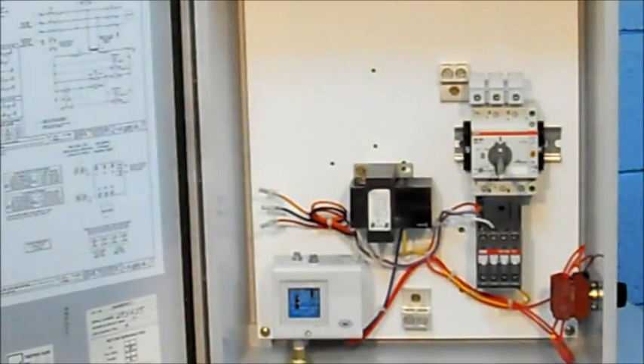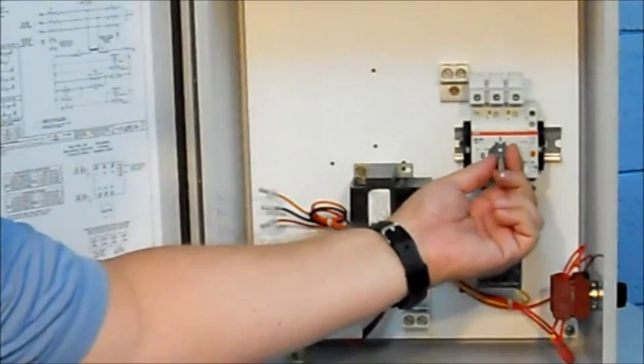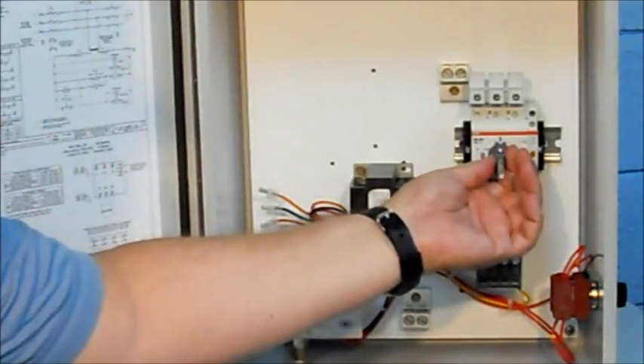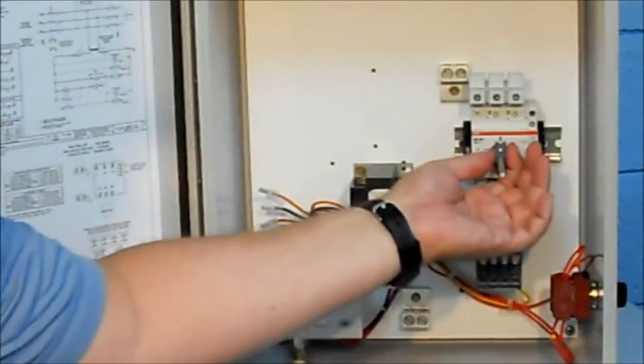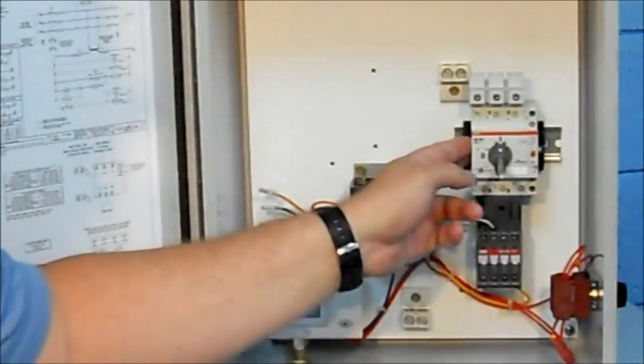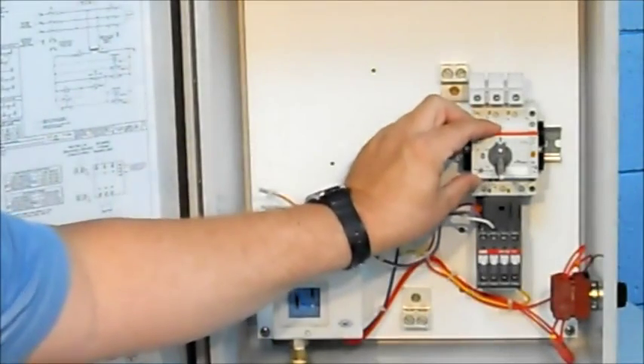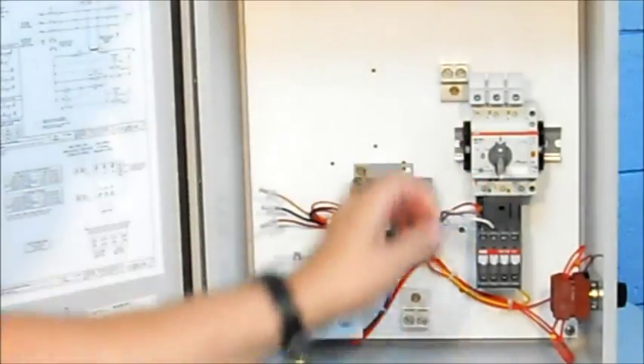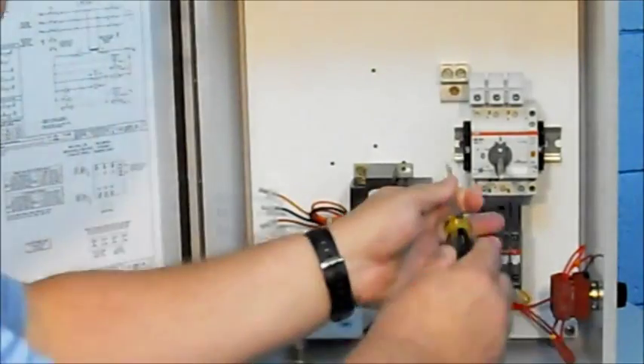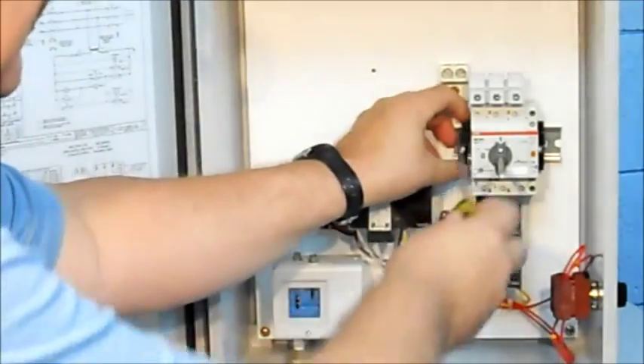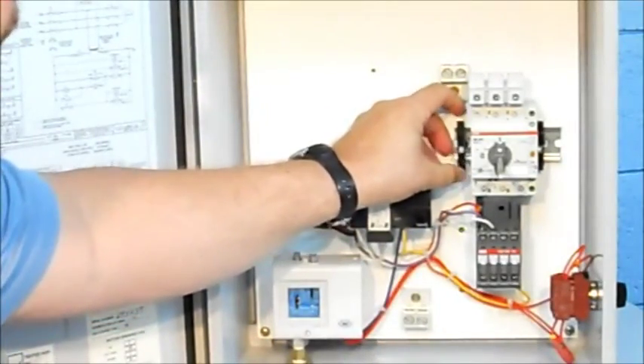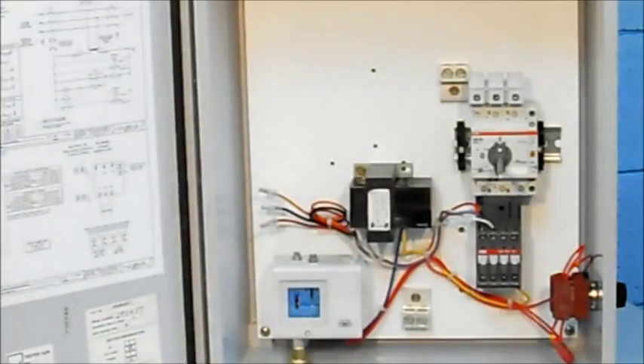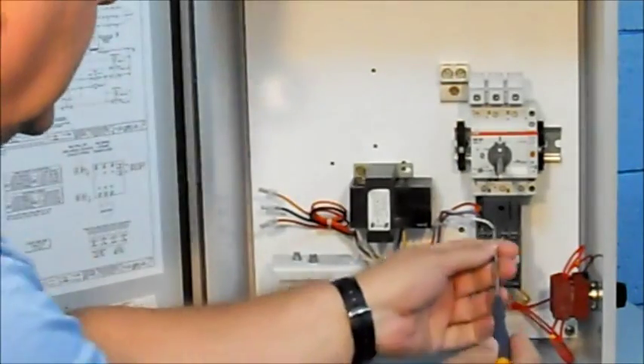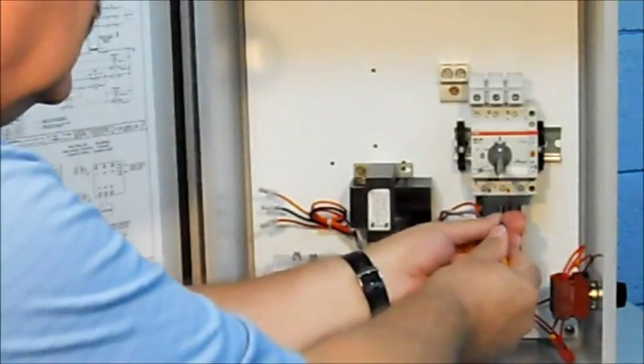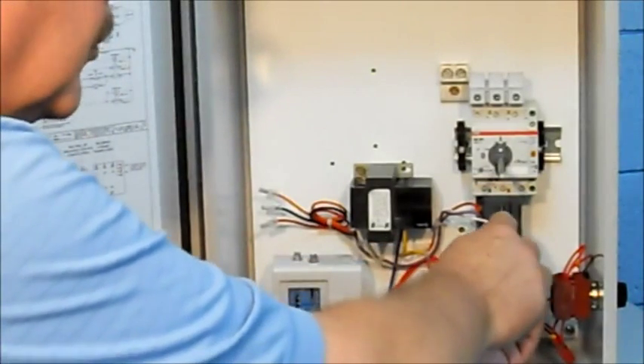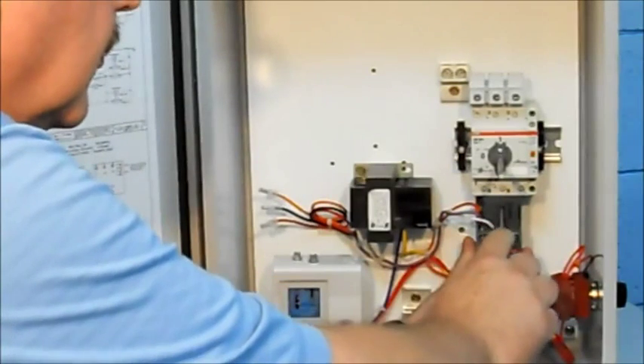Another problem we need to take a look at is the broken isolator switch operator. Many times you will see this operator has pulled away from the enclosure, and that means this disconnect needs to be replaced. In order to replace the disconnect, we take a small screwdriver, loosen the clamps on both sides that hold those in place.